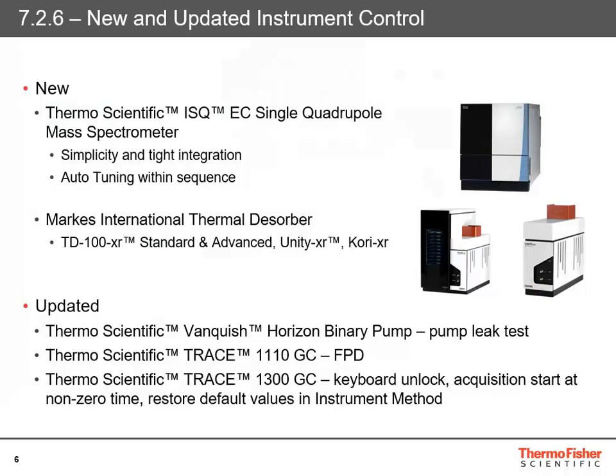The other big introduction is the Markes International Thermal Desorber — four models have been added and now have full control within Chromeleon. There are also a few updated drivers: the Vanquish Horizon Binary Pump adds a new leak test, the Trace 1110 GC has an FPD detector added, and the Trace 1300 GC has had improvements around keyboard unlocking, the ability to acquire data at a non-zero time, and instrument method improvements.